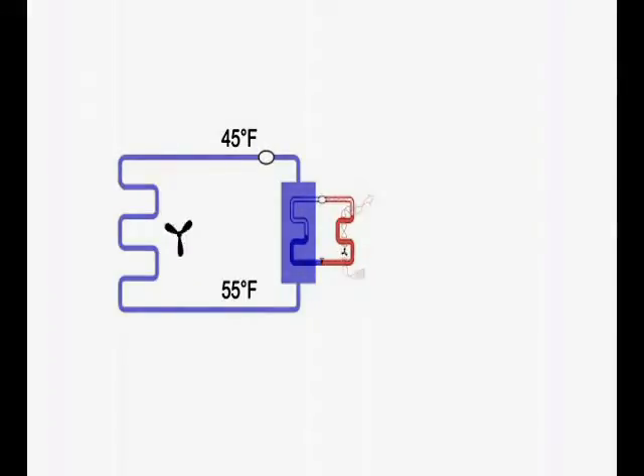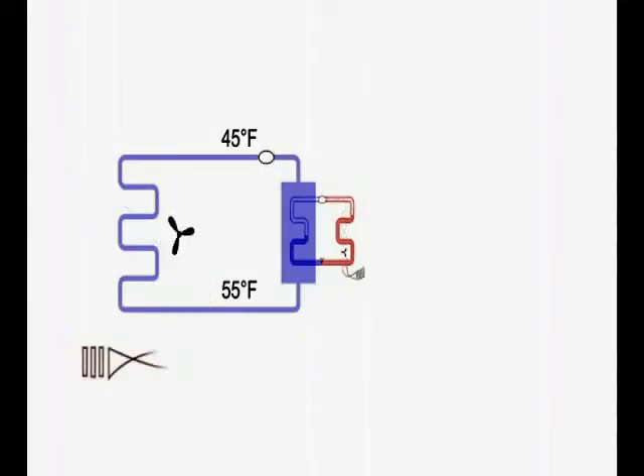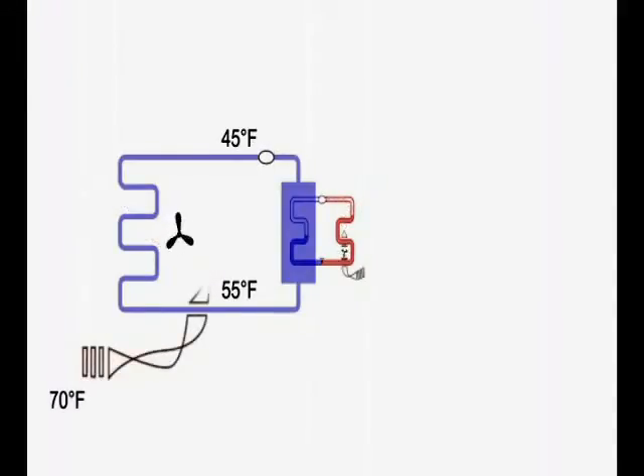The air handling unit then blows air across coils of chilled water rather than coils of chilled coolant, as we saw in previous examples, thereby cooling 70-degree return air to 50 degrees for distribution through ducts.